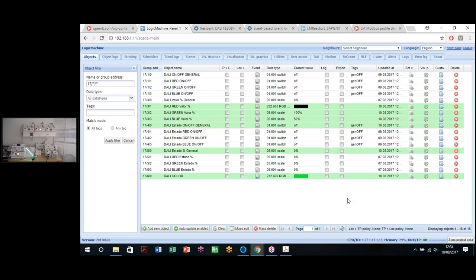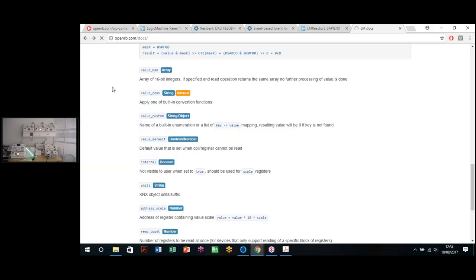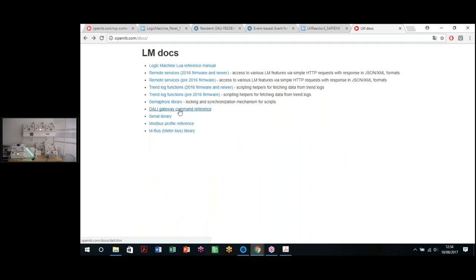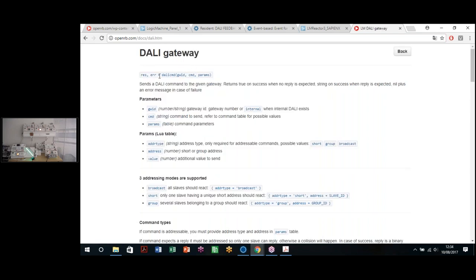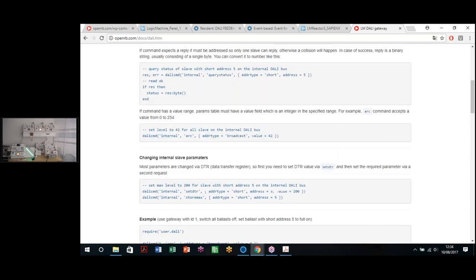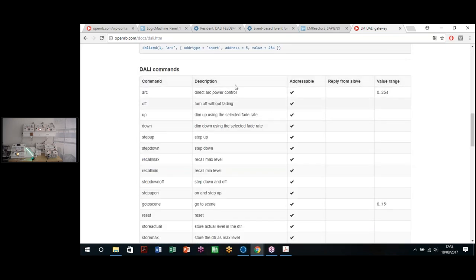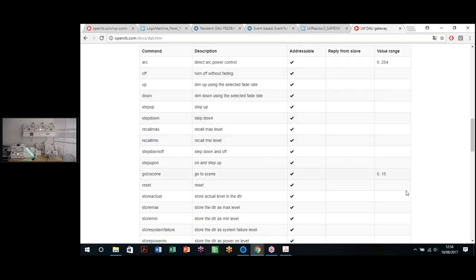Also, there are a lot of scripts that we can use and create to control our DALI device. We also can do some sort of configuration to the DALI ballasts. We can find information on how to configure these ballasts using the docs and the web page, the DALI Gateway command reference. When we go to this document, we can see that we can send commands to the DALI ballast. These are all the available commands that we can send, with the certain type of information that we will need, if it's addressable, if we will expect a reply.